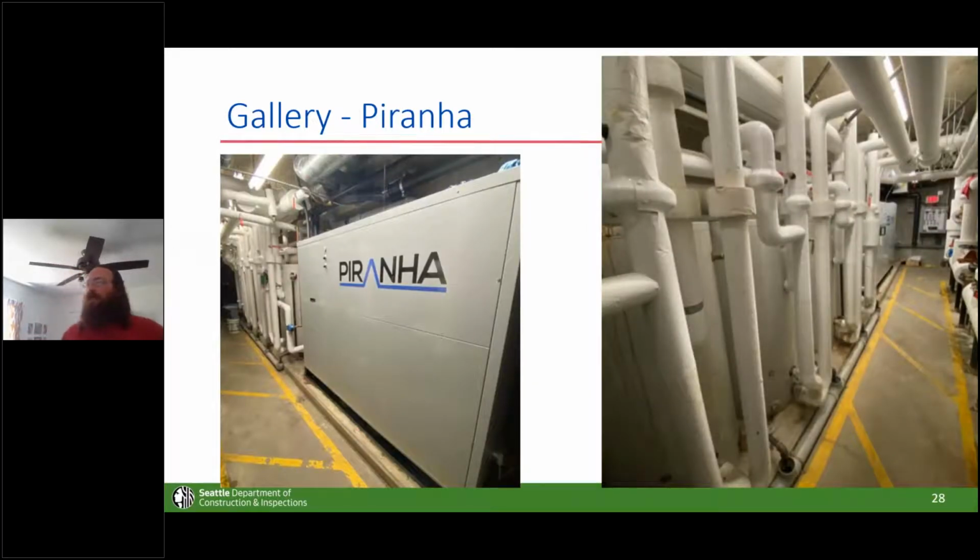Yeah, so a sewage system consists of a sewage holding tank. You're routing all of your wastewater to it, and then your sidecar is pumping that and making hot water to the side. One thing you want to be careful about is not locating this system below your sanitary connection in elevation, because that would introduce needing a lift station to then pump it back up to your sanitary sewer connection. So you want to have gravity get you there, and then water-to-water heat pumps to gravity out, right?